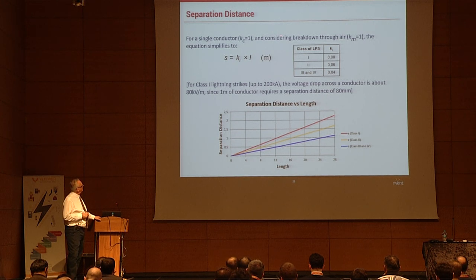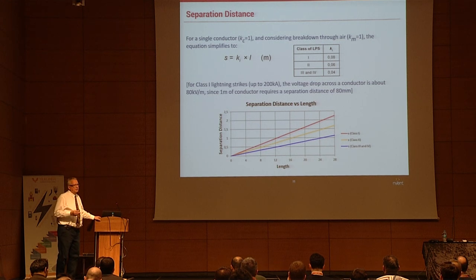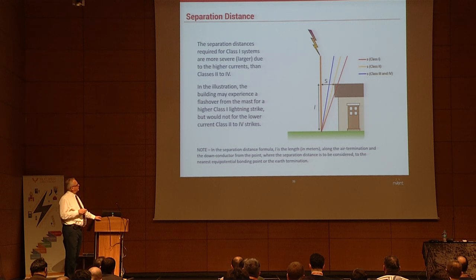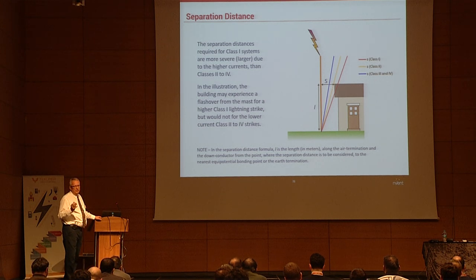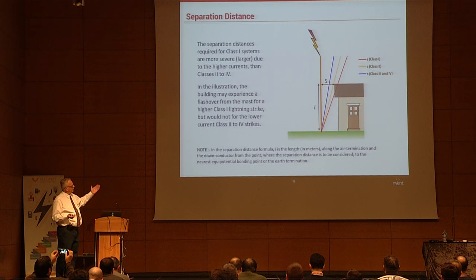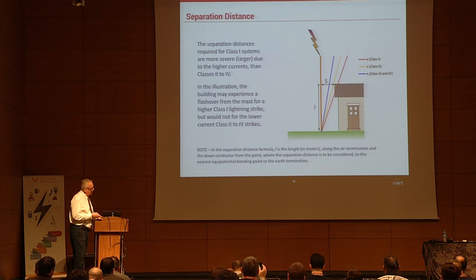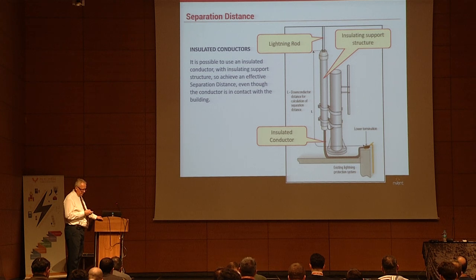Setting Km and Kc to one simplifies the formula. The curve for classes one through three indicates the cable length and separation distance. Class one is the most conservative and would overlap with the roof; class two almost touches the roof; class three and four may pass but you still need to calculate. You're strongly advised to always do the calculation for separation distance.